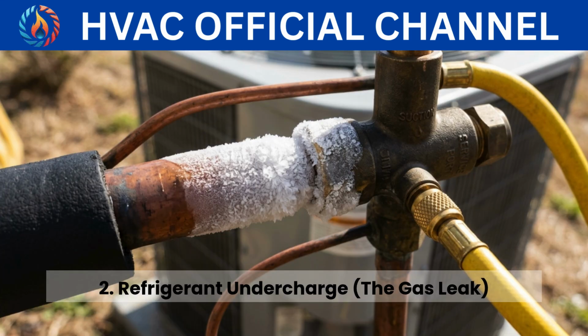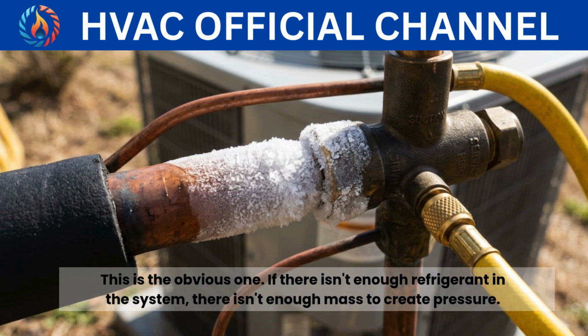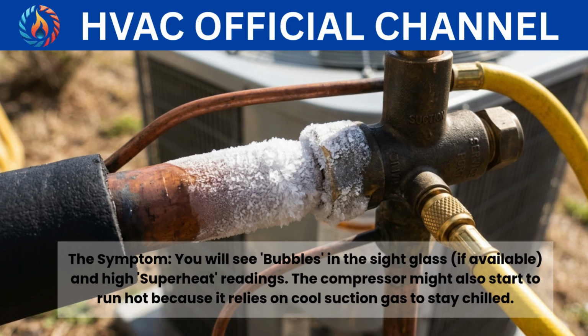2. Refrigerant undercharge, the gas leak. This is the obvious one. If there isn't enough refrigerant in the system, there isn't enough mass to create pressure. The symptom: you will see bubbles in the sight glass, if available, and high superheat readings. The compressor might also start to run hot because it relies on cool suction gas to stay chilled.